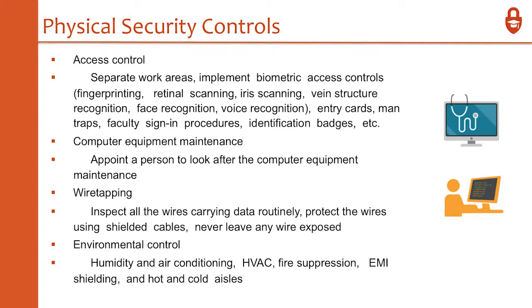Environmental controls. This is a big one. So we have humidity, air conditioning, HVAC, which is heating, ventilation, and air conditioning, fire suppression, electromagnetic interference shielding, and hot and cold aisles. So what is all this stuff about? So humidity needs to be around 60% at most, 40 to 60%. You don't want to shock the gear. That means you have too little humidity. You need more moisture in the air. If you have too much moisture in the air, it can cause corrosion and shorts in the equipment. So that's a fine line you want to maintain, and that's important. Now, that's not cheap either when you're designing a data center. So that's where the HVAC comes into play.